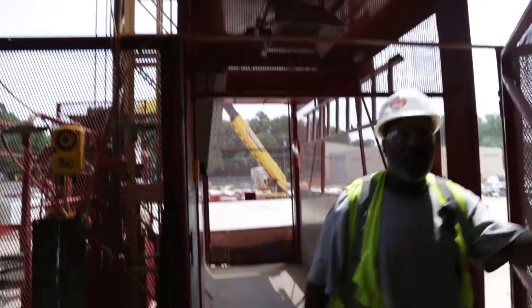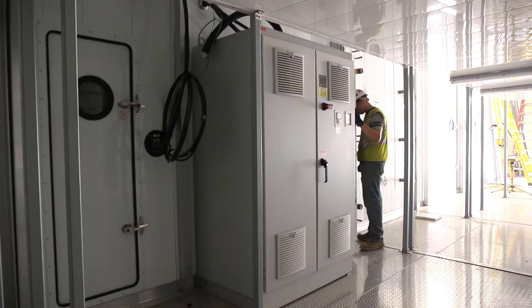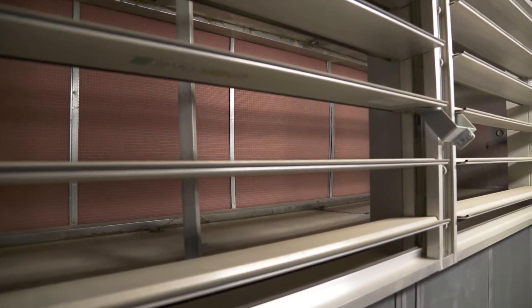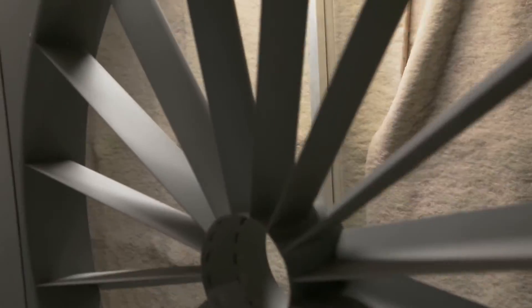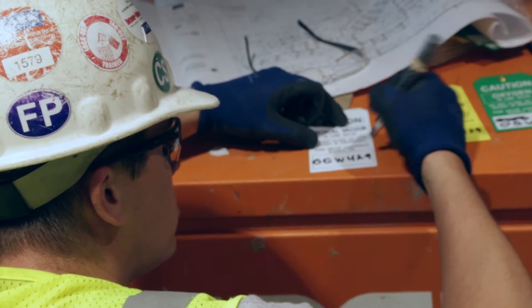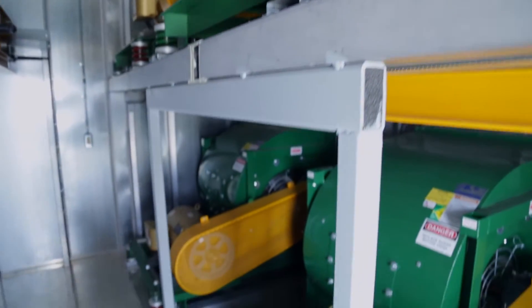Back in the hospital, there is more to inspect on the rooftop. Workers enter all of the chiller rooms to visually inspect the condition of the filters and machinery. The filter racks here are over 12 feet tall and 20 feet long. These filters are similar to what would be included in a residential HVAC installation, but are substantially larger since they handle a much greater volume of air. There are two stages of filtration beginning with a MERV-8 and progressing through a MERV-11 rack. It is critical that no airborne dirt or particulate matter pass into the air supply to the hospital. There are dozens of motors here powering fans to force air around the system, contained in isolated compartments for the safety of personnel performing maintenance while the system is running.